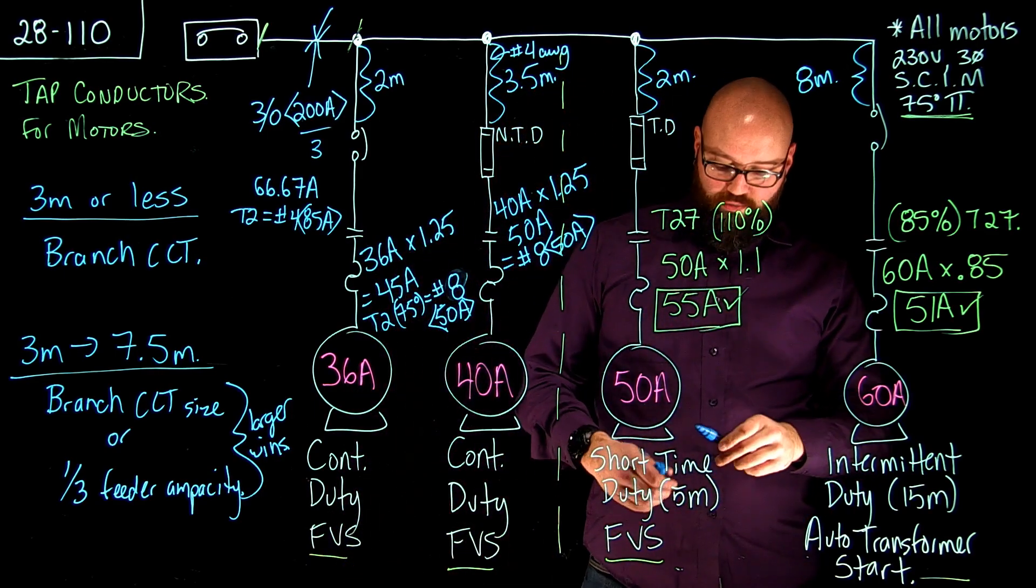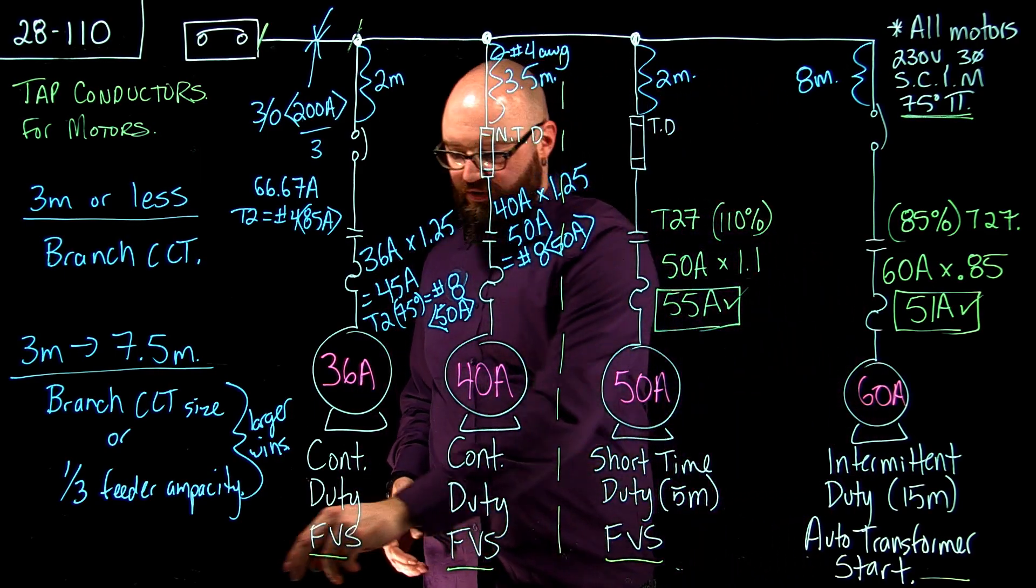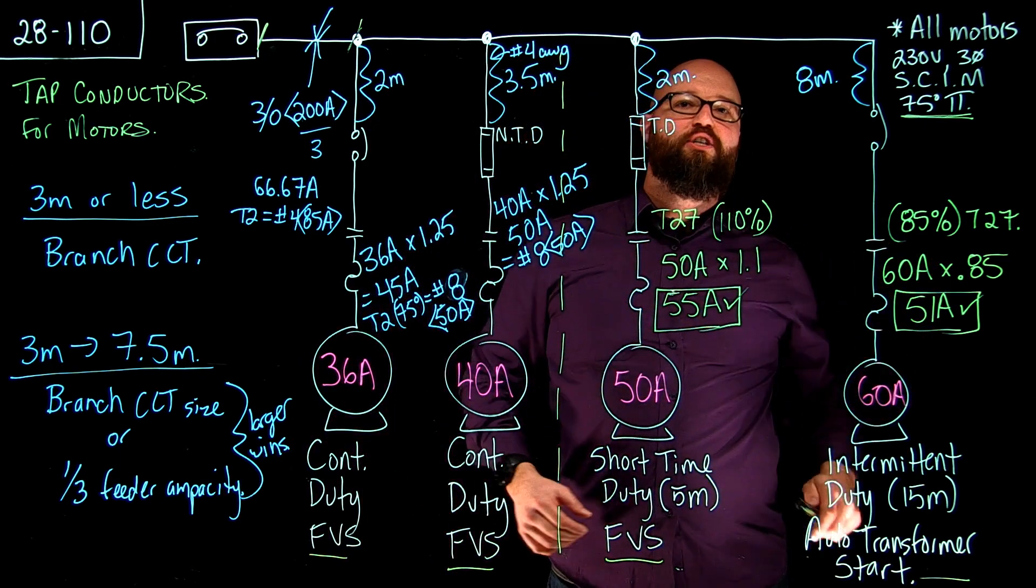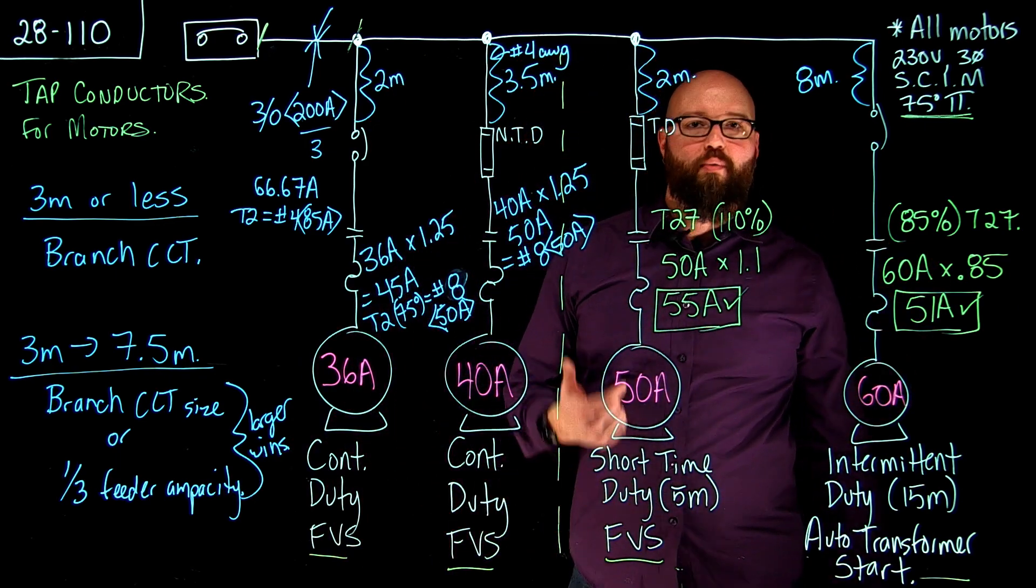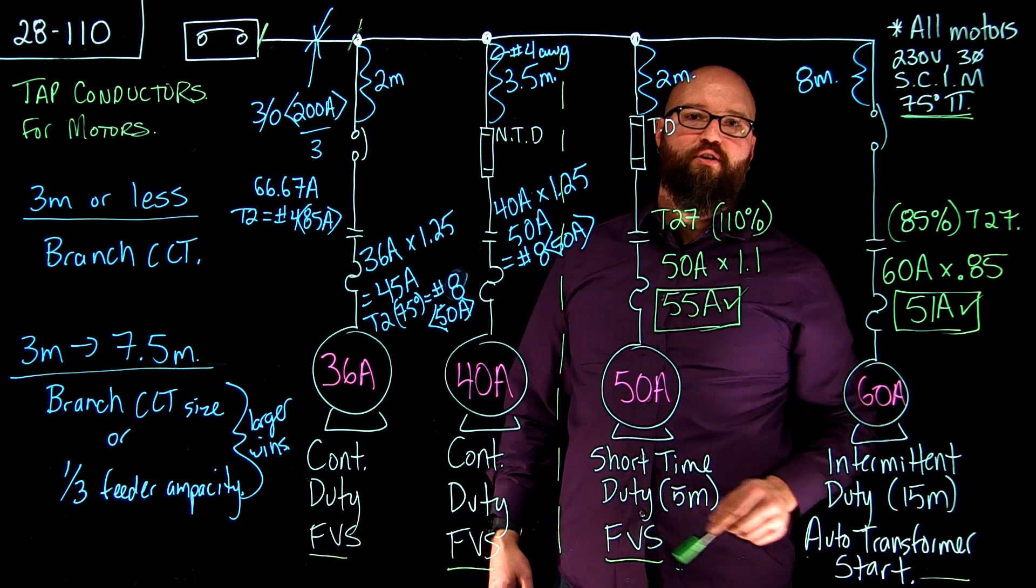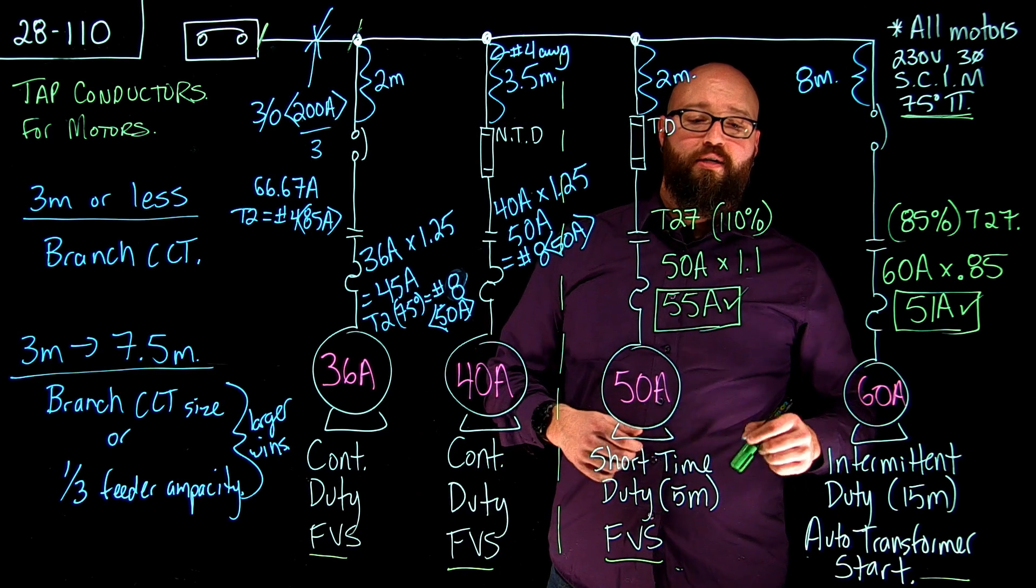Now we move into our non-continuous motors. I'm going to switch to a different color here. For our non-continuous motors I've left the calculations up from the previous video where we went to table 27 and we determined that for our short time duty of five minutes we had a 110% multiplier.